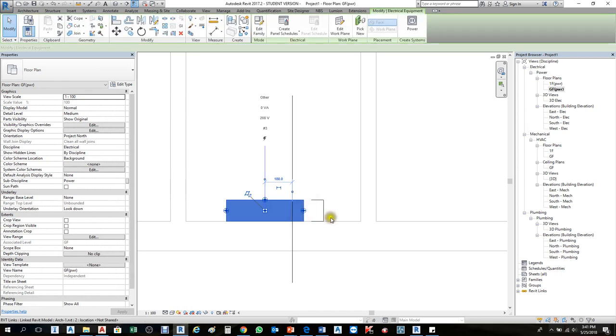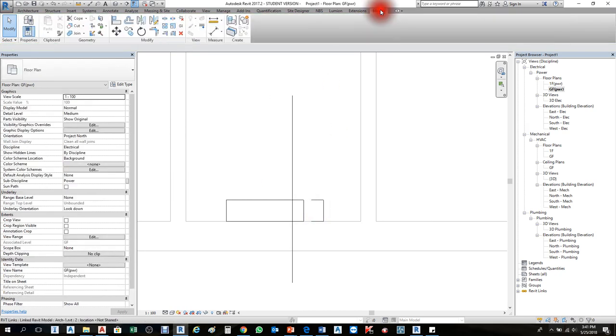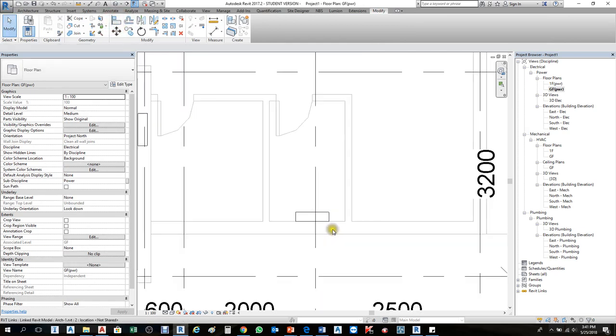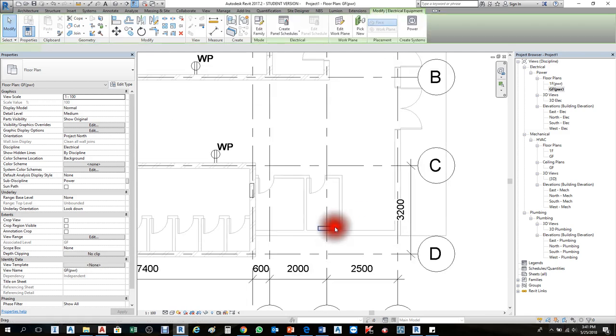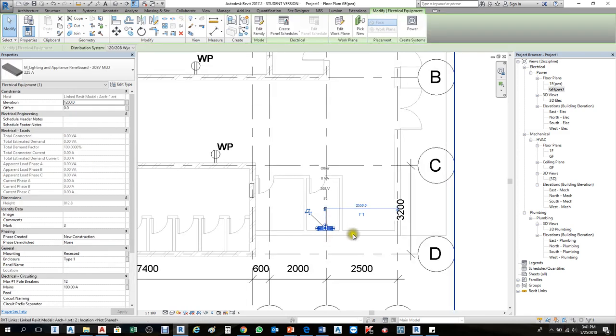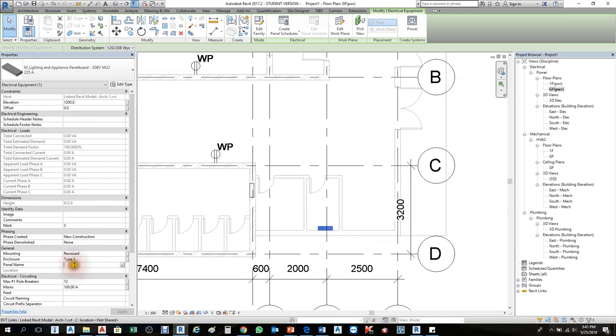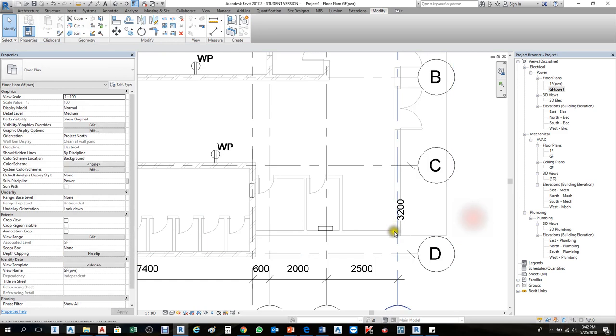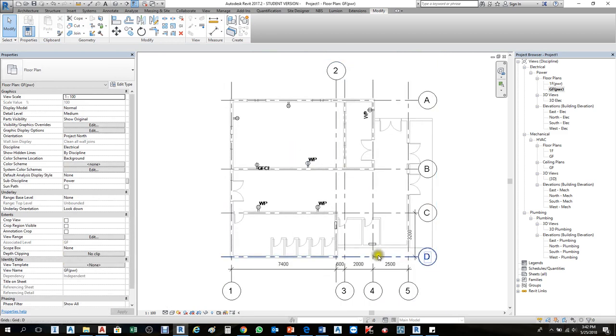Select the panel to give it a panel name. In the Properties palette, find the Panel Name field and give it a name such as P01. This panel name is important — when you create the power system and select circuits, this name will appear in the circuit selection list. If no name is given to the panel, it won't show up in the list, so be careful to always name your panels.